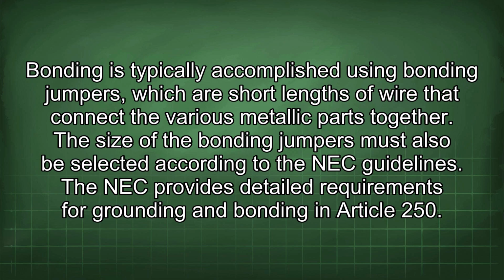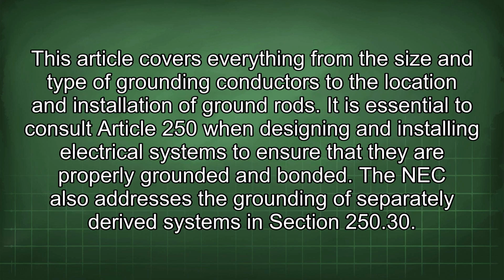The NEC provides detailed requirements for grounding and bonding in Article 250. This article covers everything from the size and type of grounding conductors to the location and installation of ground rods. It is essential to consult Article 250 when designing and installing electrical systems to ensure that they are properly grounded and bonded. The NEC also addresses the grounding of separately derived systems in Section 250.30.